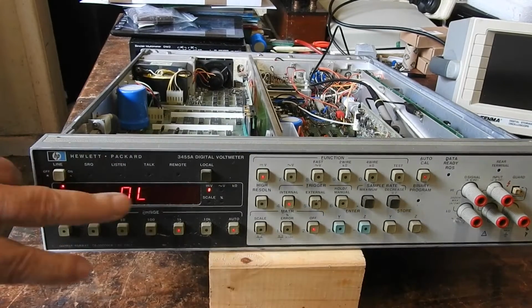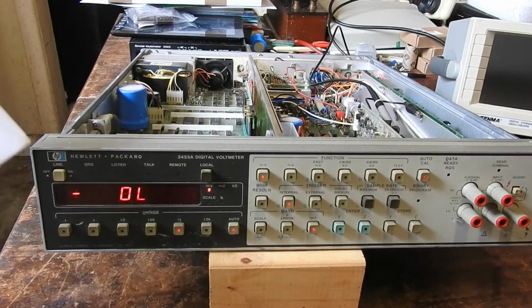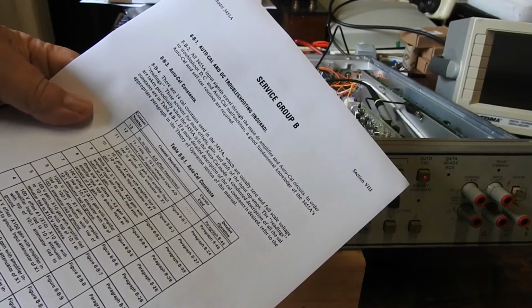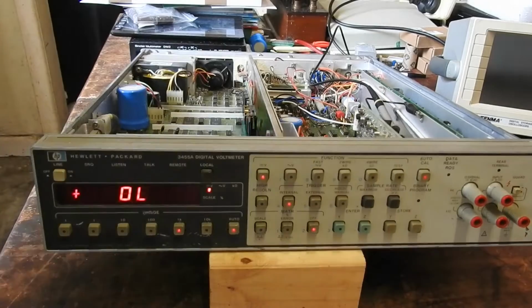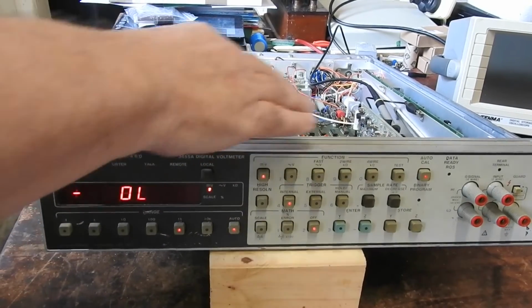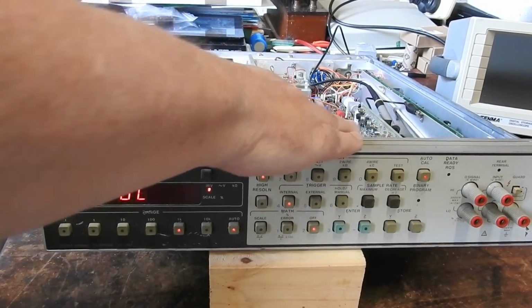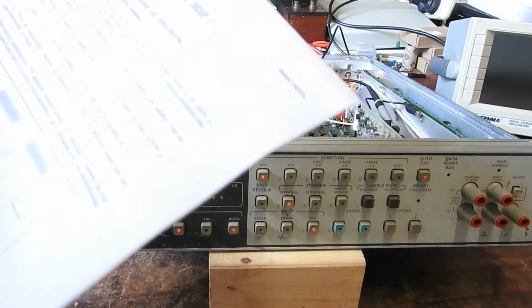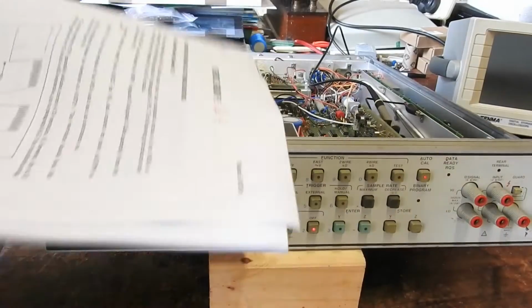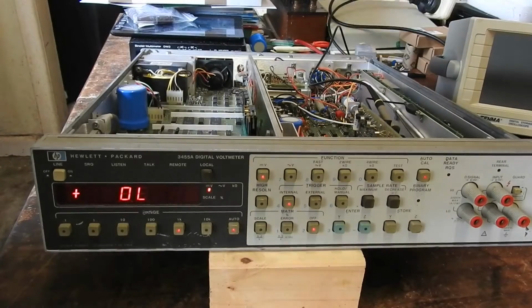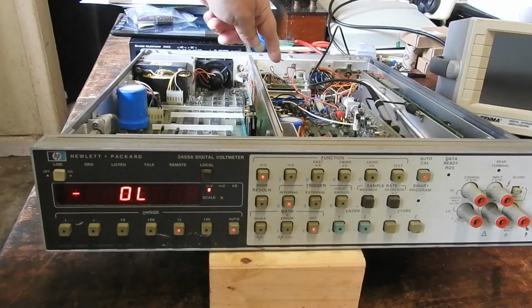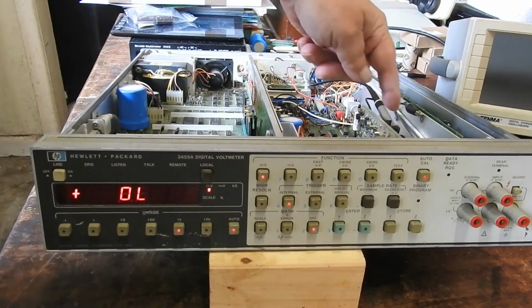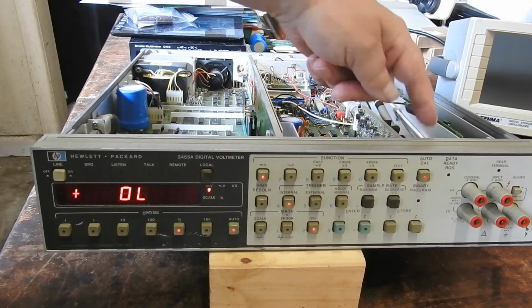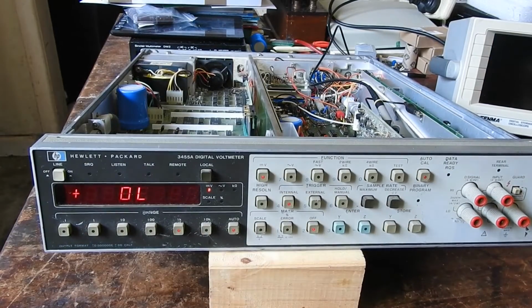Now this OL indicator on startup steers us to service group B, which is a lot of things to test, and the half split procedure that revealed that the in-guard board has a problem sends us to service group E. And both of these say to check the reference voltages, plus and minus 10, coming from the reference module, which somehow snakes its way all over the board to here. And I've done that and I didn't like what I saw.